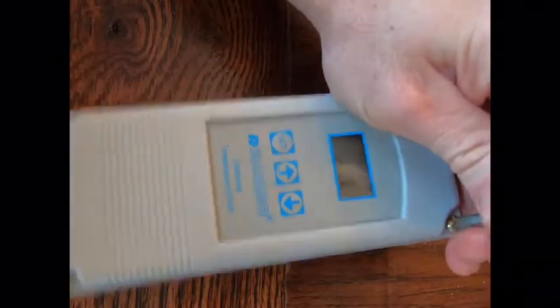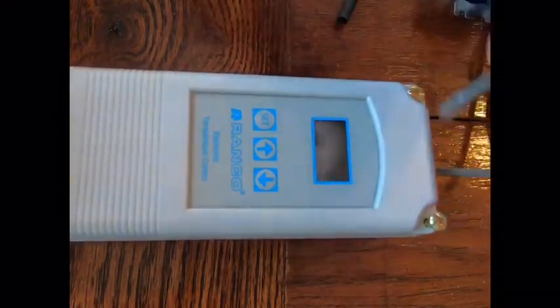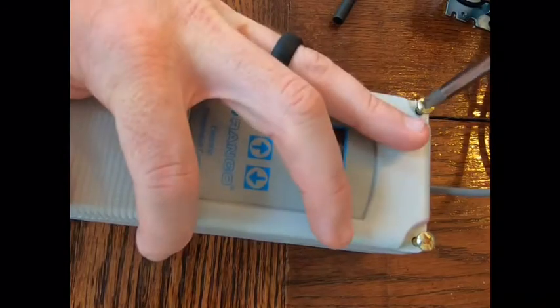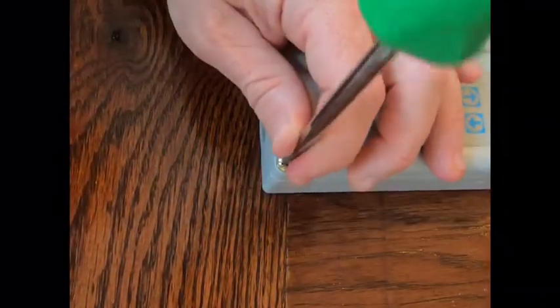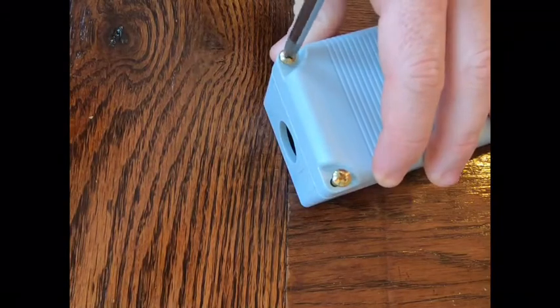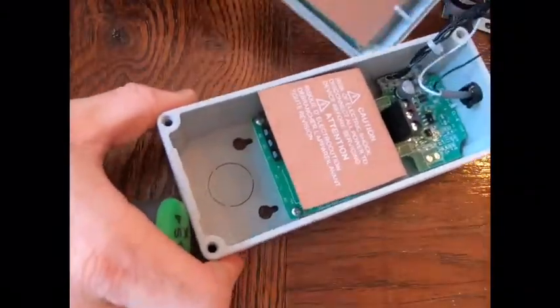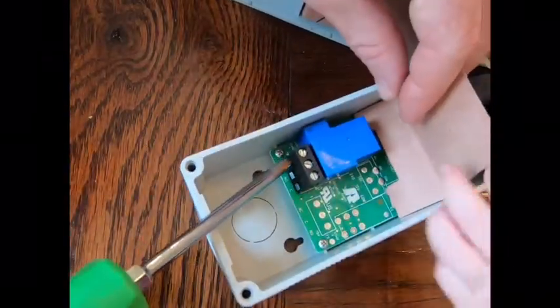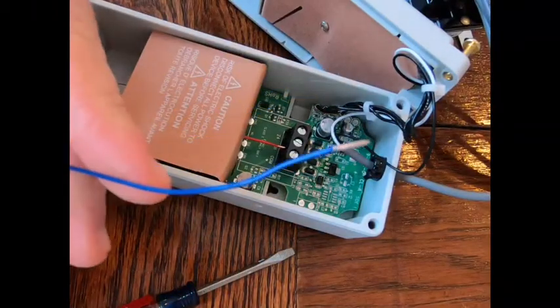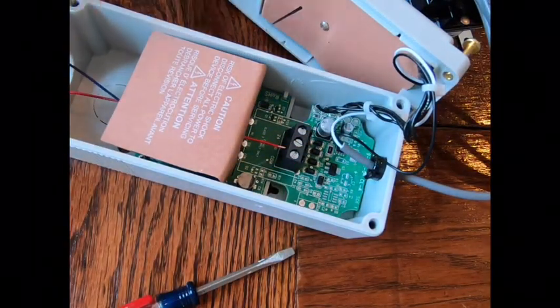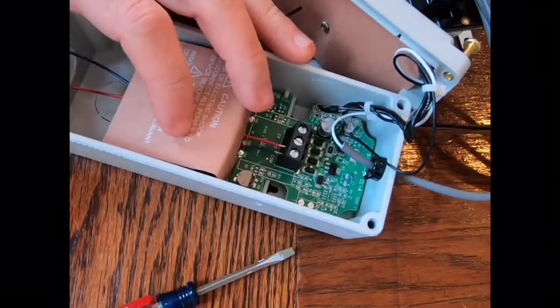First thing we'll do is get the Aquastat set up. Just take out the 4 corner screws and the faceplate will come off. Just ignore that red wire that's already in there. We'll start with wiring up the blue. So run the blue through the bottom and to the right connection, which is going to be your common. This is just thermostat wiring. Just make sure you have a long enough lead so that wherever you decide to mount your Aquastat, it can make it from there to inside your air handler.